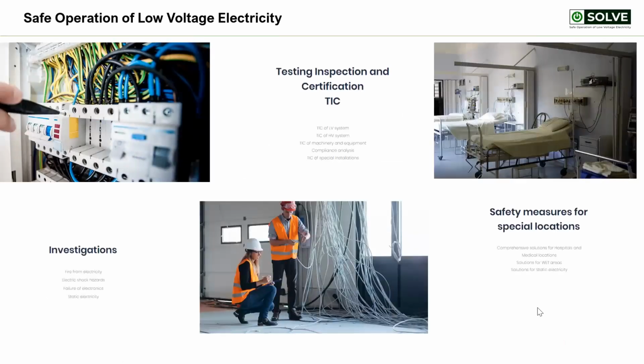So what we do is, we are very specifically going into the testing, inspection, and certification of electrical installation. The software guides our certified people on how to do the testing or the inspection. And while guiding, it also tells you some additional requirements. For example, the verification, if we carry it out through the IEC standard, of course, those are made from the European or the American perspective, whereas in India, the situation is entirely different. So we are actually Indianizing those requirements. So additional tests are sometimes required. And finally, it will be very easy to identify future faults.